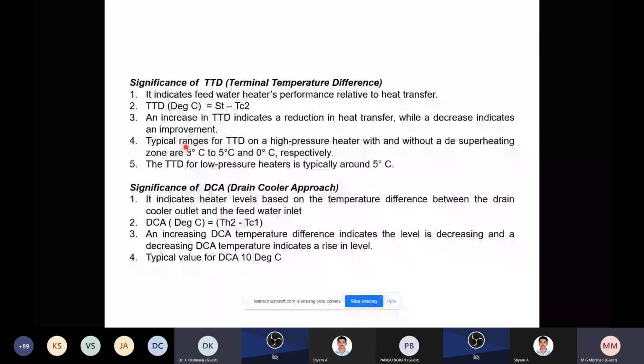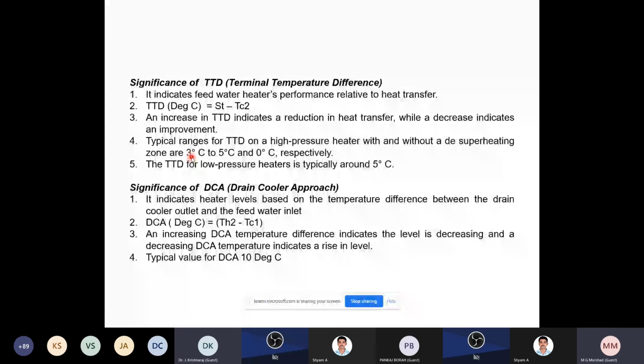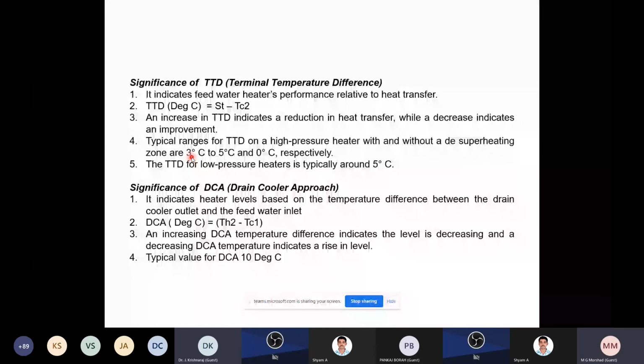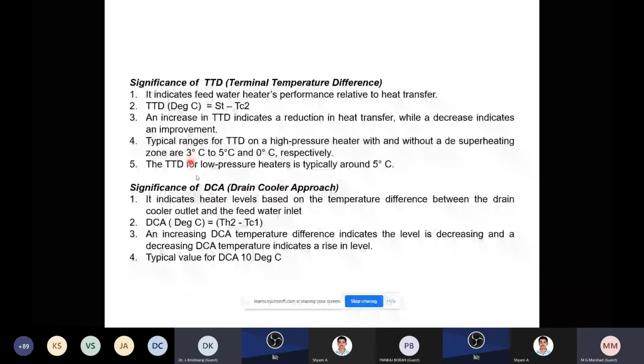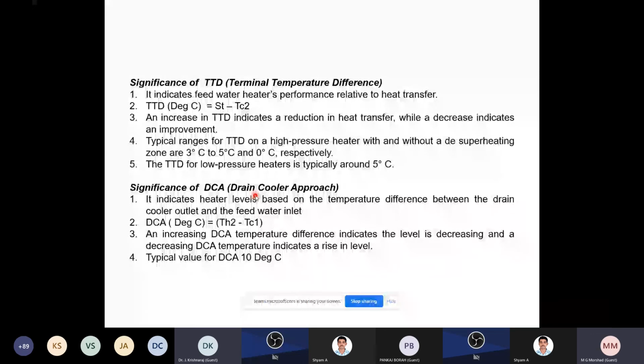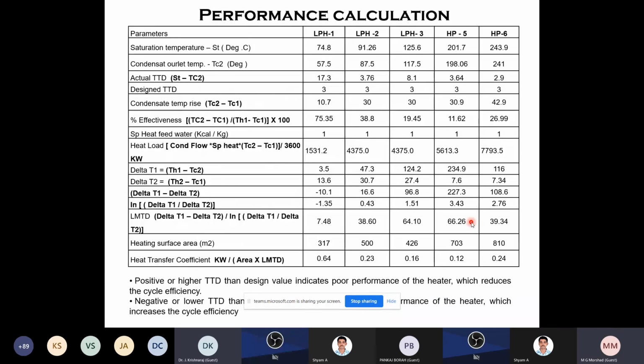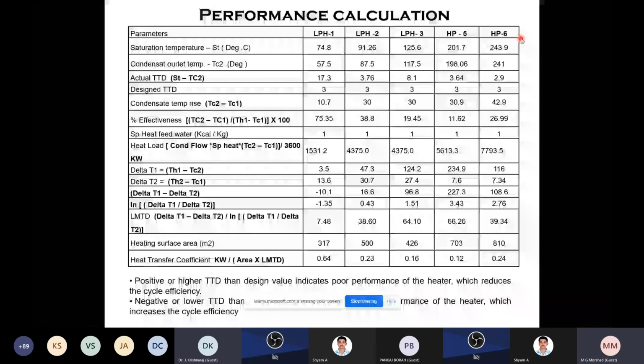Normally the TTD difference will be about 3 degrees. If the TTD is higher, the performance is very poor. If the TTD is on the lower side, the performance of the heater is good. So normally 3 to 5 degrees will be the standard. The drain cooler approach is the level of the condensate, and the typical temperature will be 10 degrees. So we have established a plot like this, with the saturation temperature for LP heaters 4 up to 6. We put all these things in. So these are the designated TTDs.